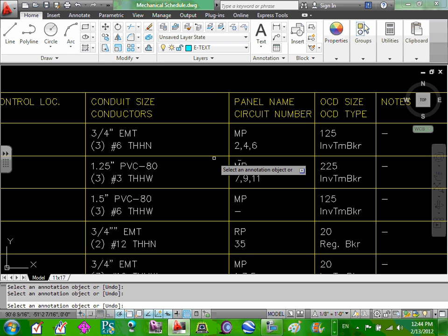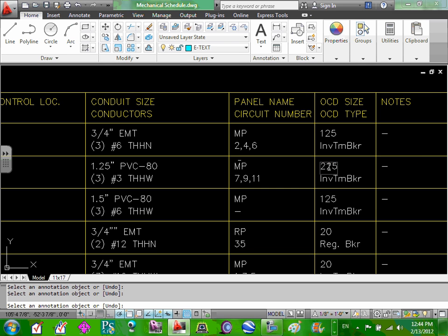Okay, so let's go. Now, I trust that this is what your numbers are, guys. 7,9,11, okay? Then, overcurrent protection device. Do you guys remember what the sheet says for the overcurrent protection device for this one? It was 110. The manufacturer is telling us it's 110. If you guys go to page 18, under maximum fuse size, 110. So I'm going to size it 110. Size this one 110 for them.